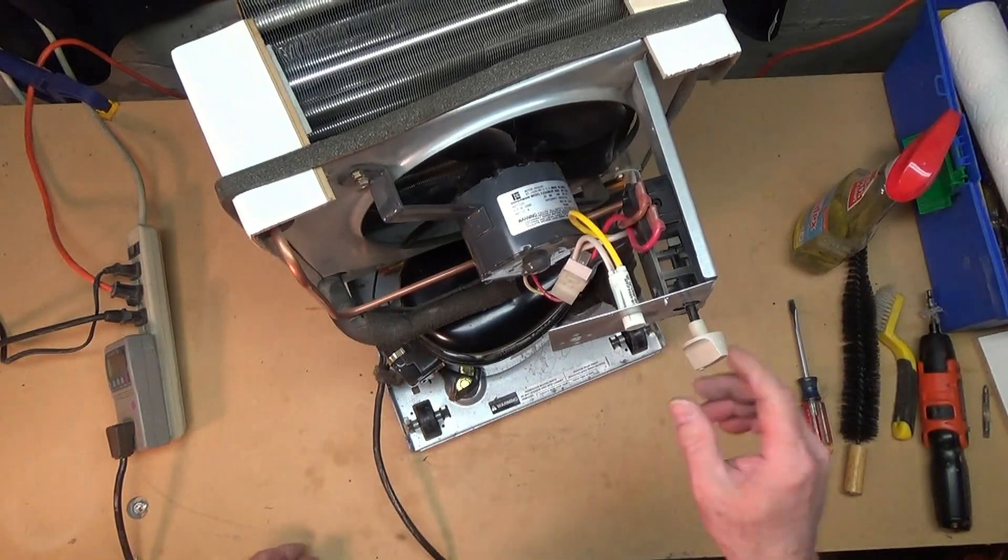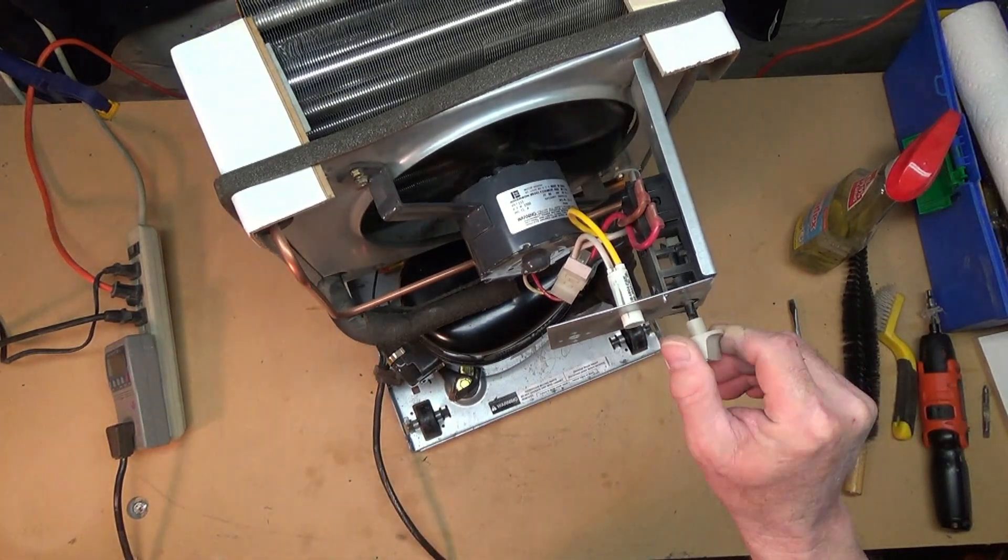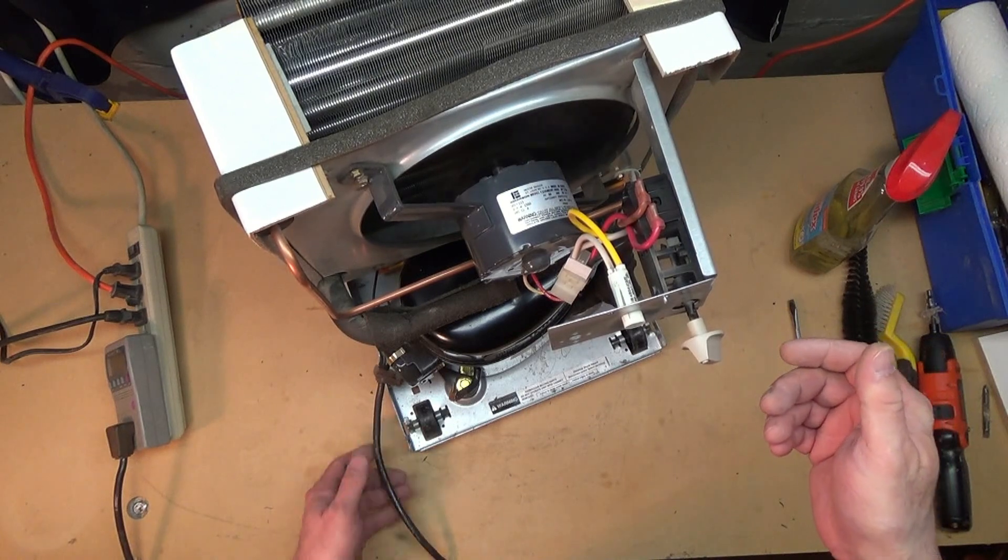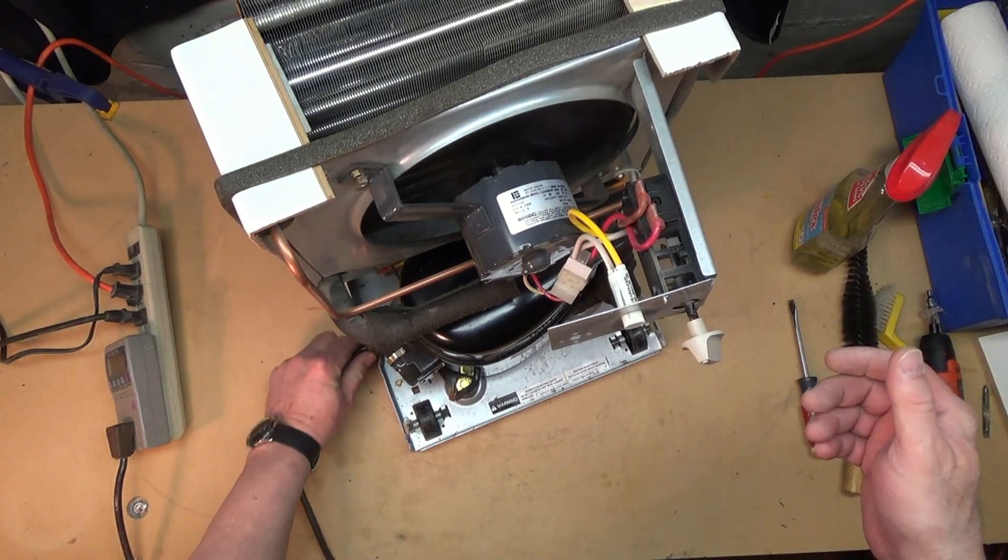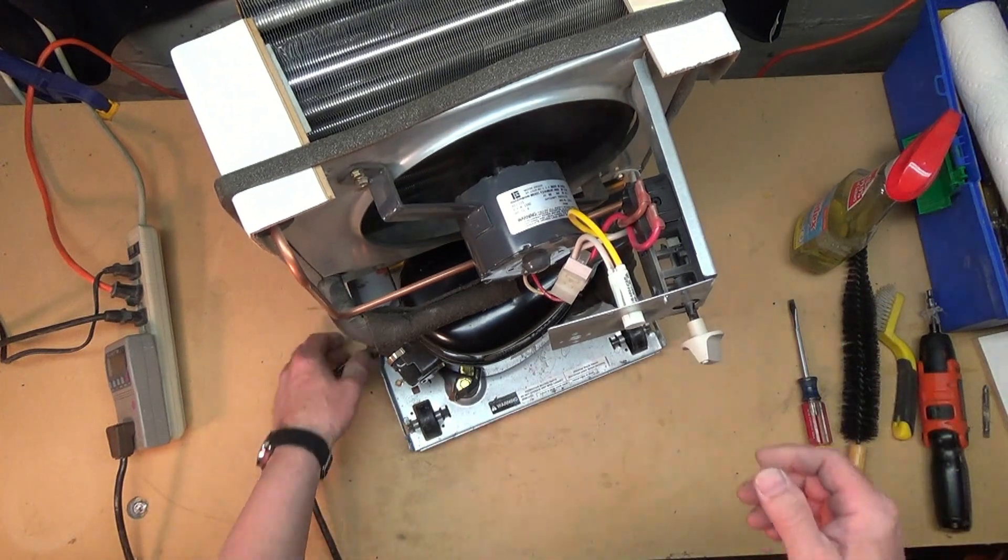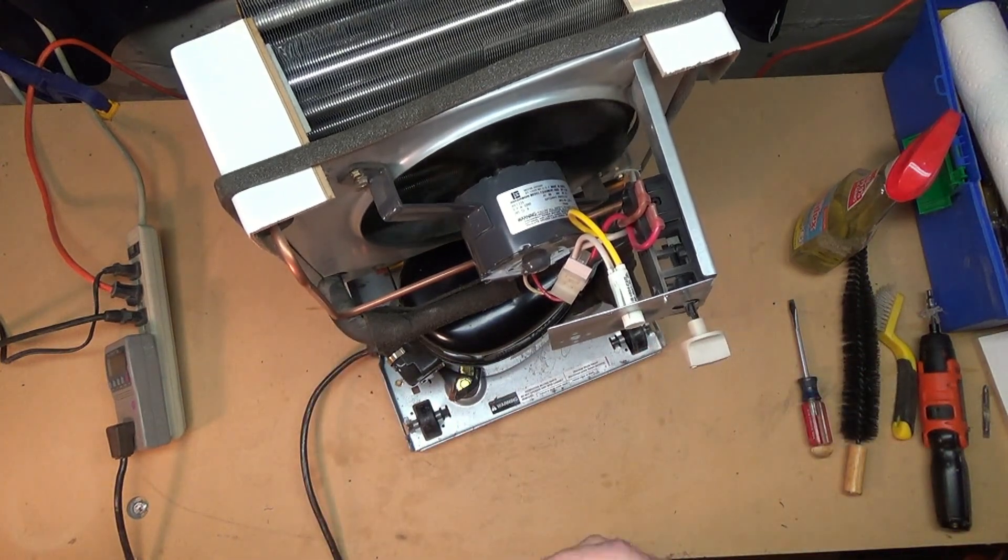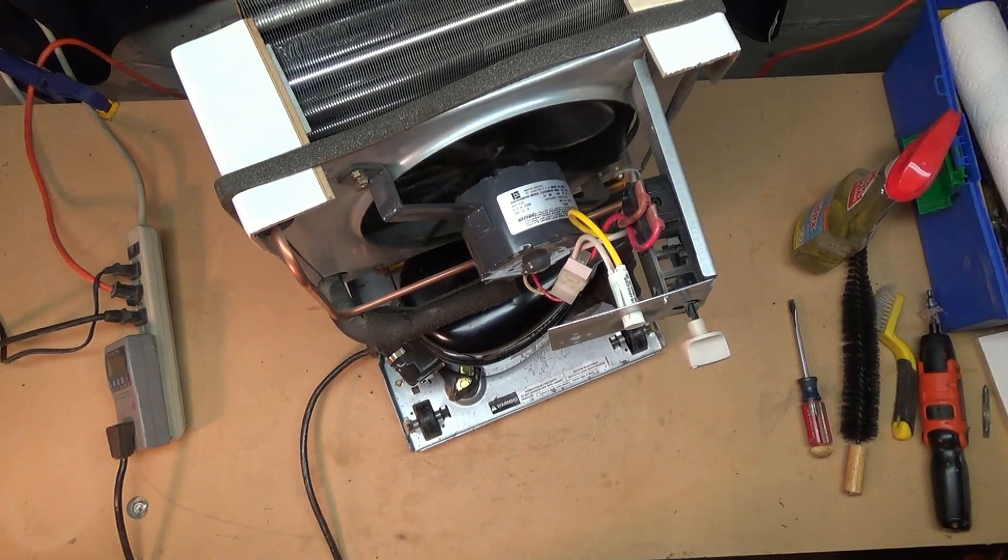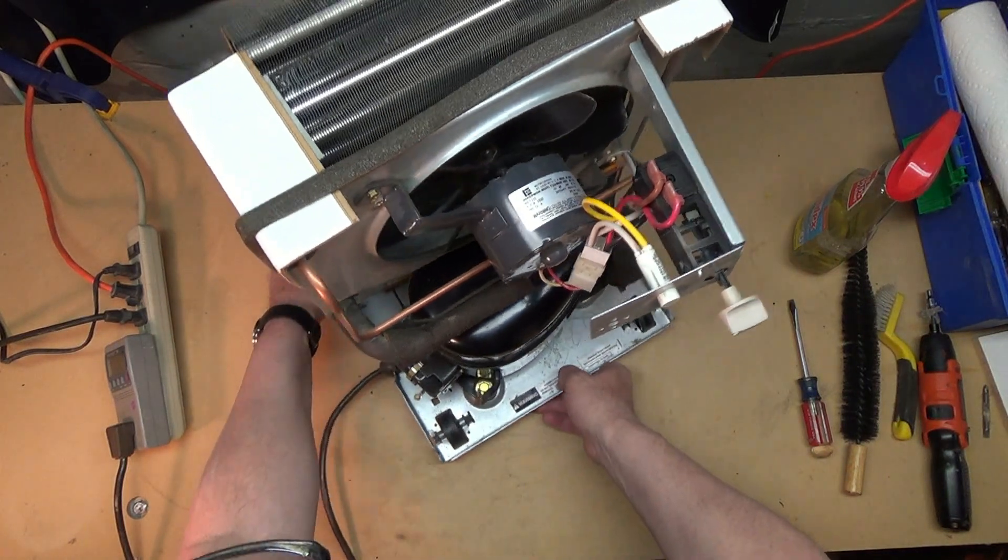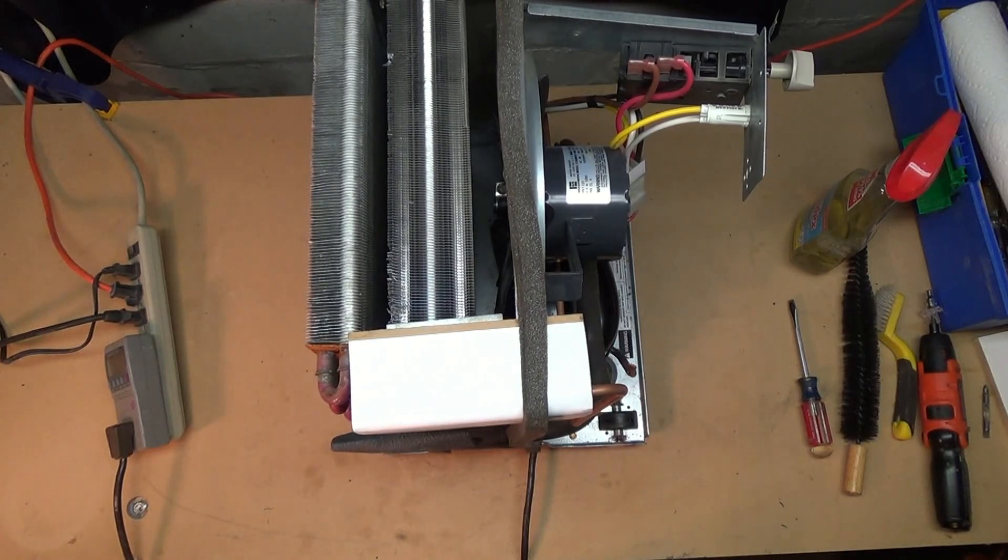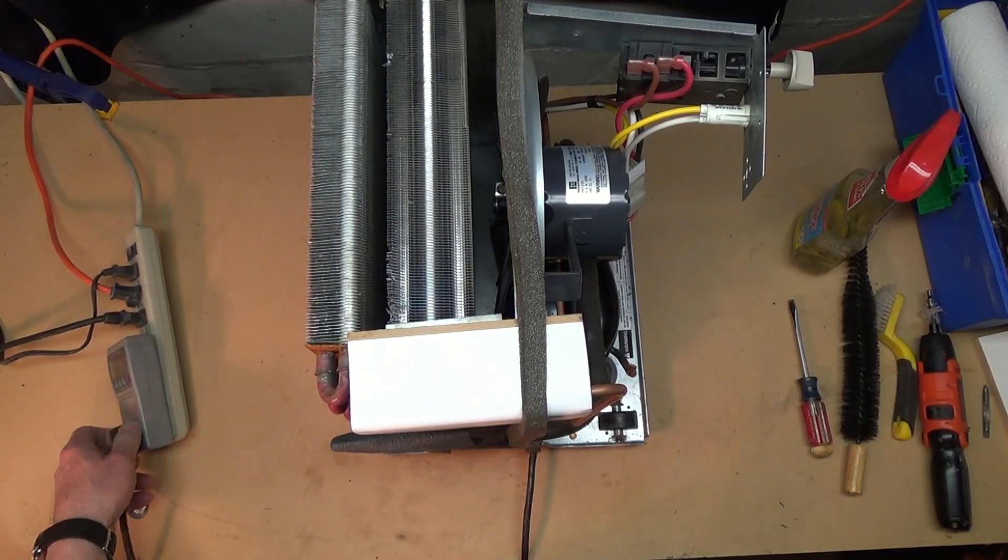So from everything I could see, this unit comes on when I ask it to, it gets cold when I ask it to. I've cleaned the coils with a brush and air. I've straightened the coils out so that air will flow across them in the future. I'm going to put the case back on this and I'm going to return it to the person who owns it now for the summer. Thanks for bringing it in.